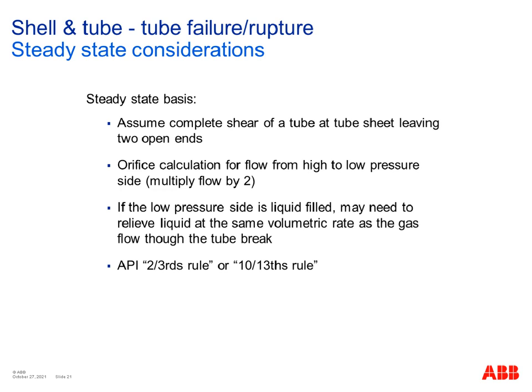It's often talked about, but it's worth noting that ASME test pressure is now 1.3 times design, which would make it the 76% rule or the 10/13 rule. And you now need to take temperature into account when determining the test pressure. So you need to account for the temperature difference that would be in place when you're actually in that relief scenario, or in that overpressure scenario, sorry. You need to account for that higher temperature. So for BS, British Standard 5500 vessels, the test pressure to design pressure ratio would be at least 1.43. So this would give you another fraction again. This would be the 7/10 rule. So it does get a bit more complicated when you start thinking about what the actual test pressure situation is with regard to the low pressure side. So as before, you need to consider your scenario individually and not rely on rules of thumb.